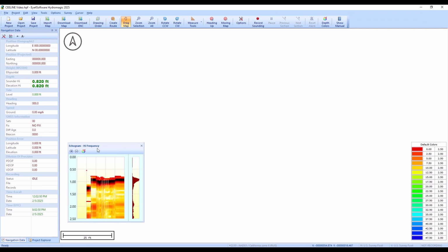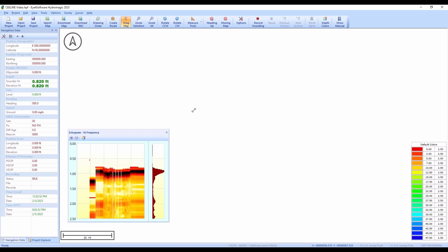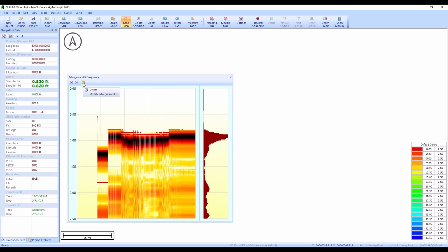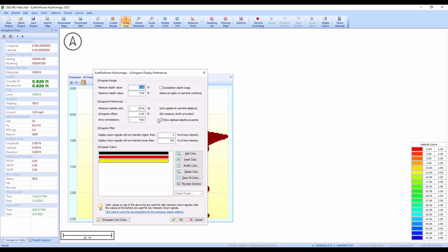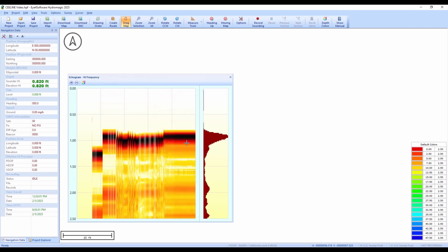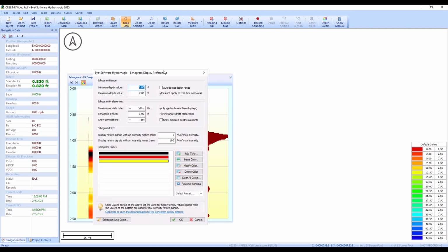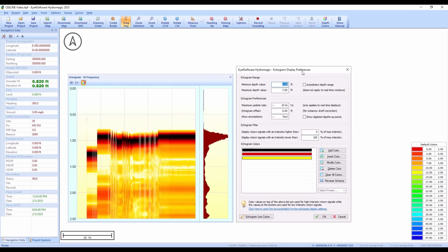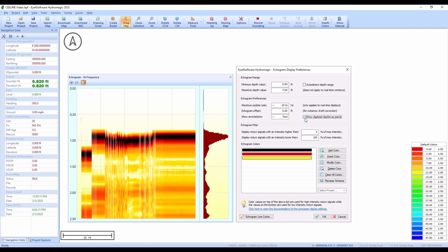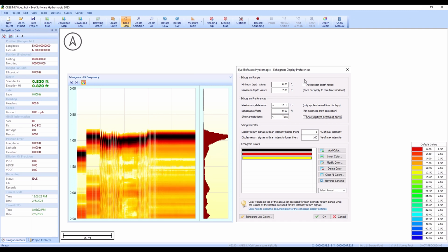So that's the echogram. On the setup options for the echogram itself, we click on colors. The default actually is to remove the digitized depths as points, to make it a little bit cleaner when it first opens up. When you've installed Hydromagic, this will be unchecked. So if you want to see your digitized points in your echogram display, then you have to go in and check this. And you can change the range of the minimum maximum depth of display.